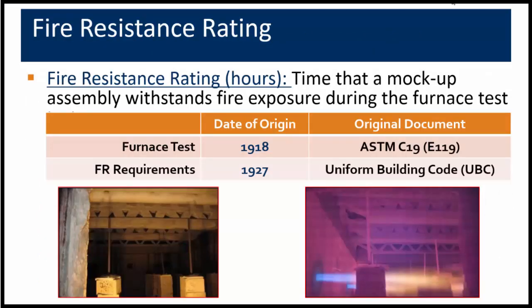Building codes have largely determined when fire resistance rated structures are needed, and protecting a neighboring building in close proximity to a property line is another example. In some cases where the owner has a large aversion to property loss, such as a telecommunication facility, structural fire resistance can play an important role in maintaining business continuity. Fire resistance rating can be defined as the time that a mock-up assembly withstands the fire exposure during the furnace test. The tested assembly is a mock-up and the fire exposure is from a furnace test — not necessarily representative of actual construction or a real fire.